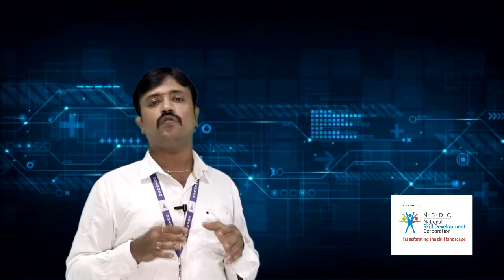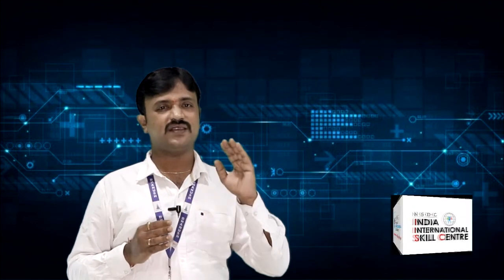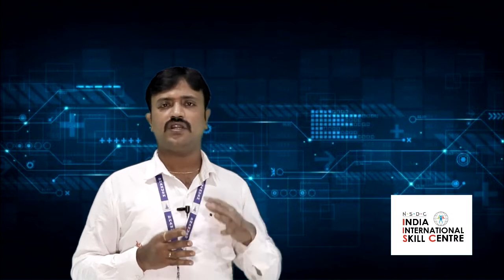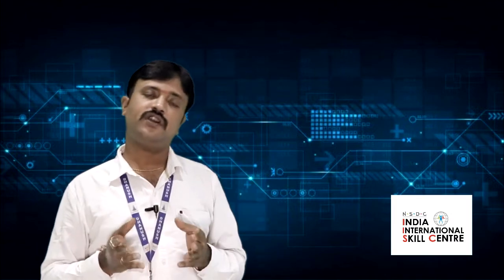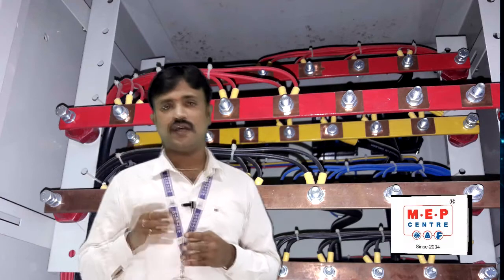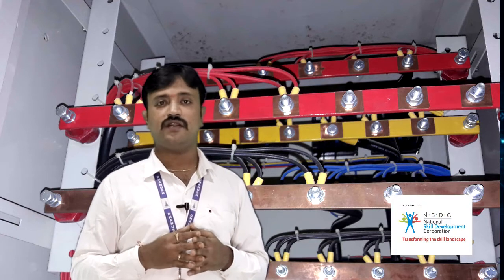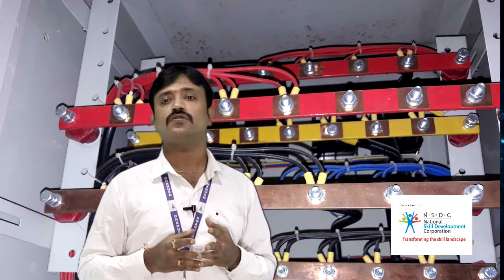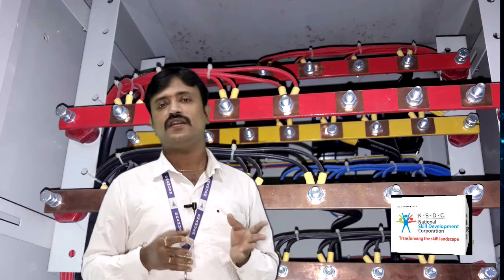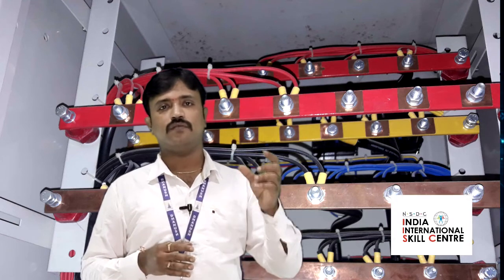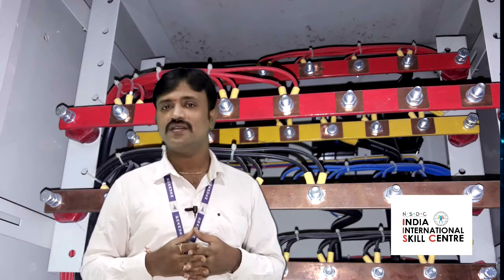Now we need to define the size of the cable tray required to pass the cables from one point to another point. So we are going to study the cable tray calculation, where we need to find out the width of the cable tray, the depth of the cable tray, as well as the weight of your cables, to give it to the manufacturer. That is about the cable trays. The next one is the bus bars. Now, what are bus bars? Generally, if your current is very low, we go with cables. But if your current is very huge, we go with components called bus bars, where in the main distribution board panel and sub main distribution board panel, we put a bus bar. So we need to calculate that bus bar sizing.